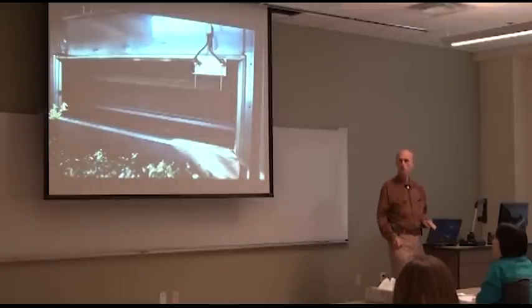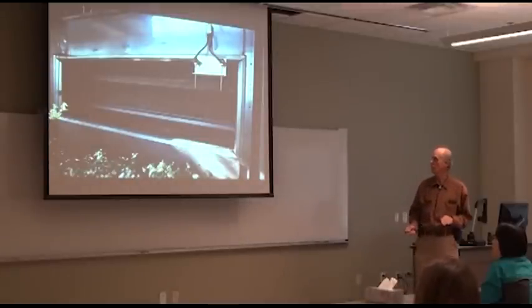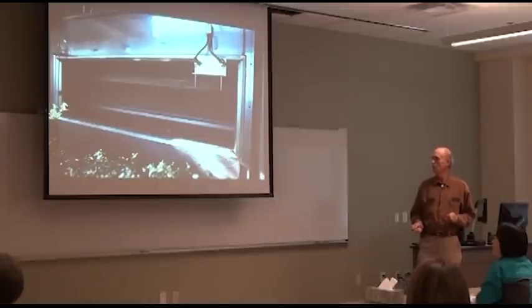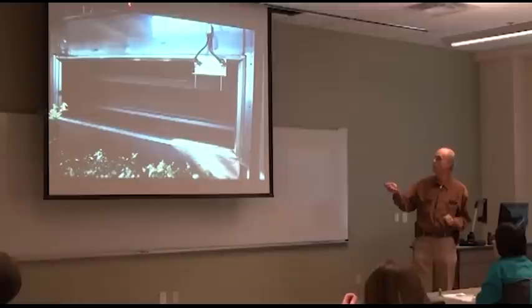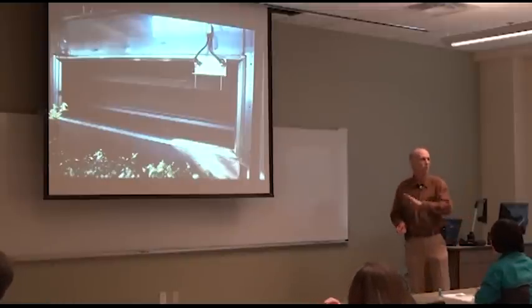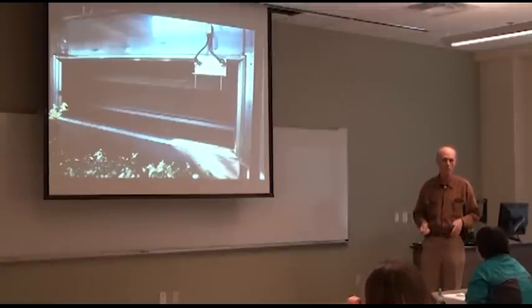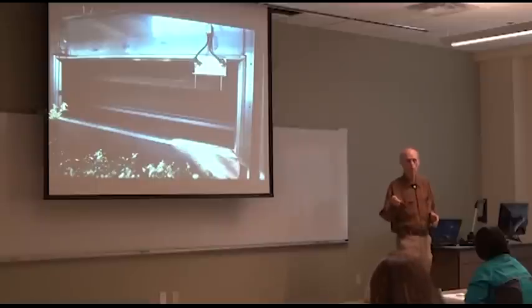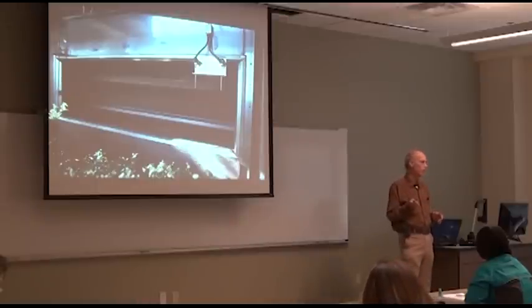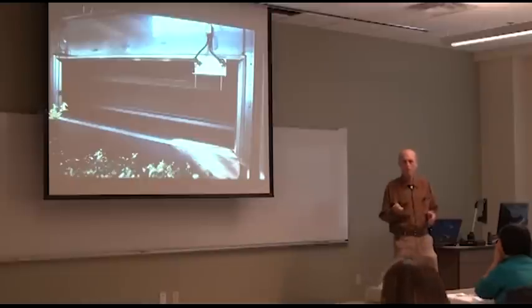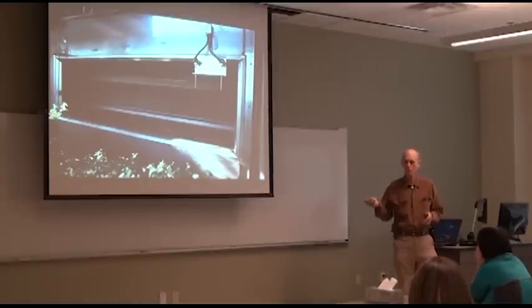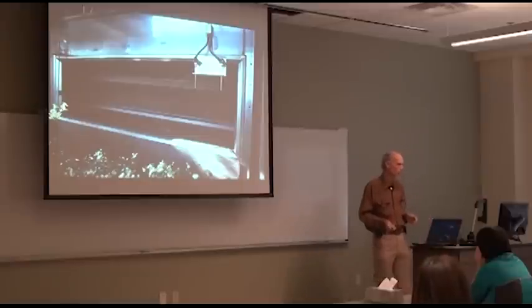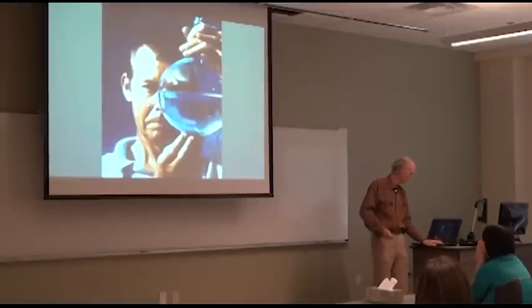This is the discharge mouth of an air handling unit. These were large units. They're 12 feet wide by 9 feet high and about as long as this room, about 30 feet long. Each one of them moved 50,000 cubic feet per minute. And there were 25 of them in Biosphere 2 in order to maintain temperature and humidity conditions. And I'm going to talk more about the detail of their operation a little later.